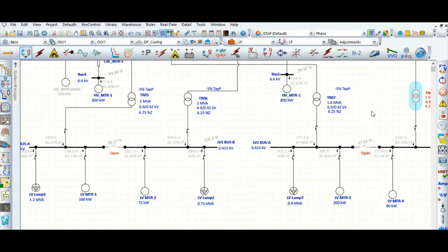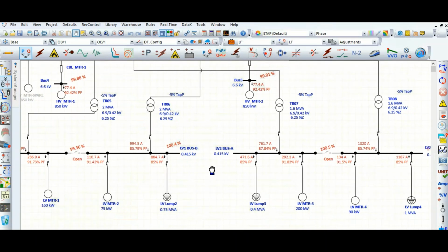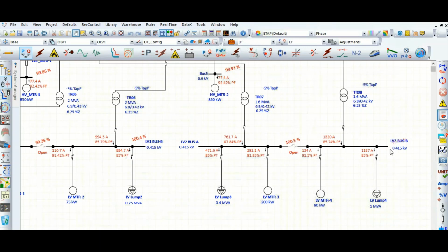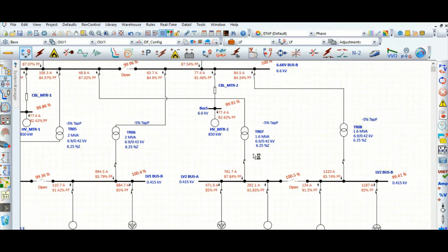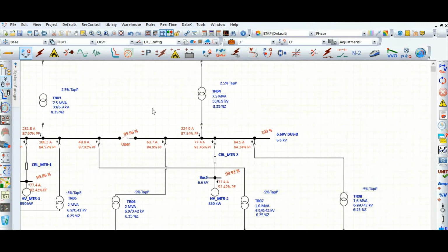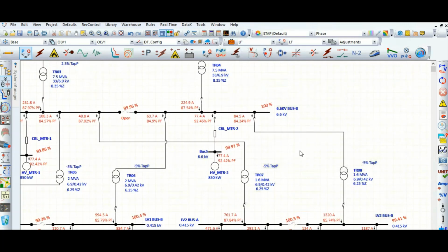Let's run. You can see this is now 100%. Bus voltage is now improved. This is 99.41%, so there is no alert, marginal or critical. This is quite an acceptable limit. So in this way we can improve the bus voltage profile.